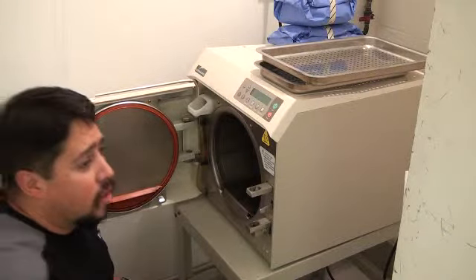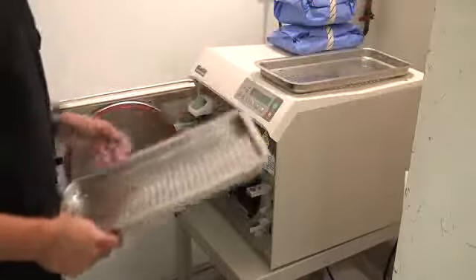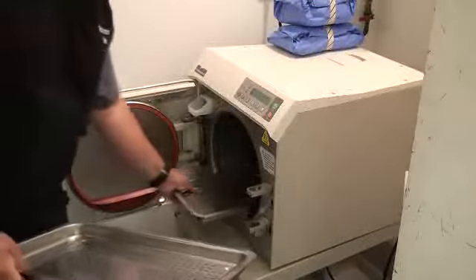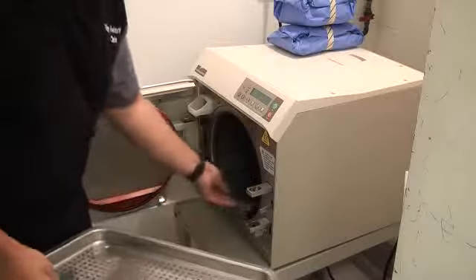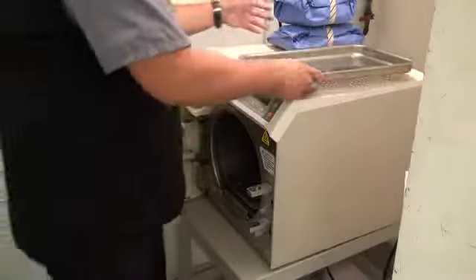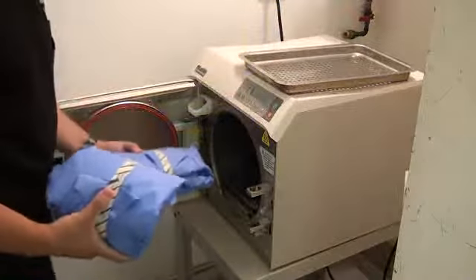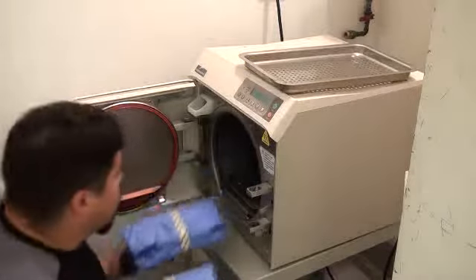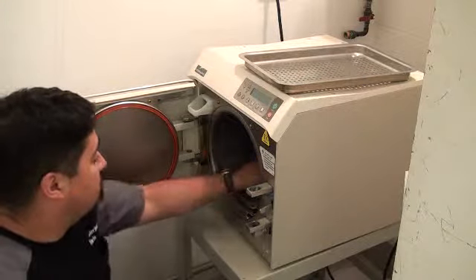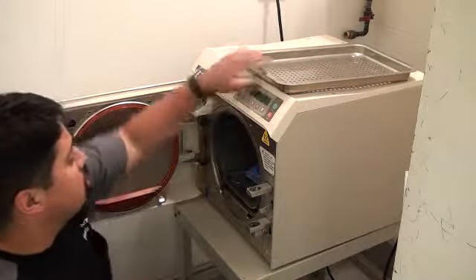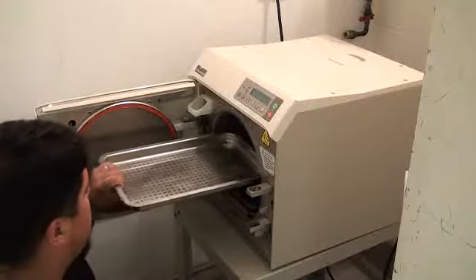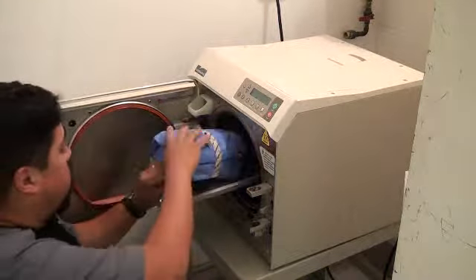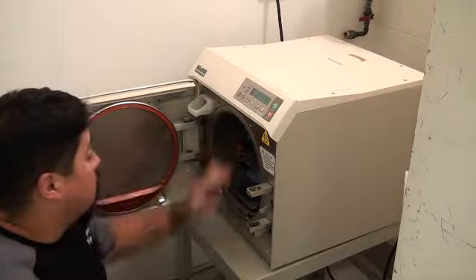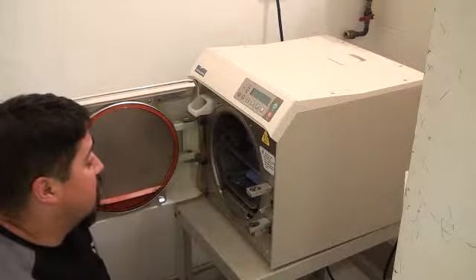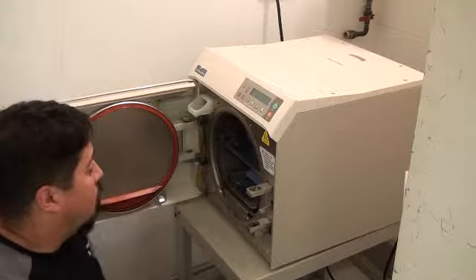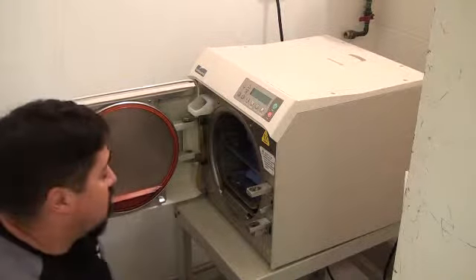When packing an autoclave, there are trays in here to separate, so you don't have to stack things up on top of each other. For instance, I've already autoclaved these, but this is the pack and gown I did earlier. I will put them in the autoclave in the center of the trays. Put this tray up above it and place this pack in the center of the tray. You don't want the sides of the packs touching any of the walls. The only surface that should be touching the pack is the bottom that sits on the tray.